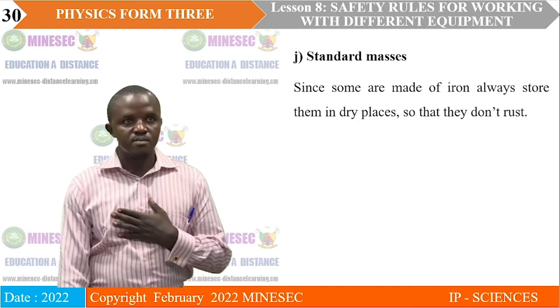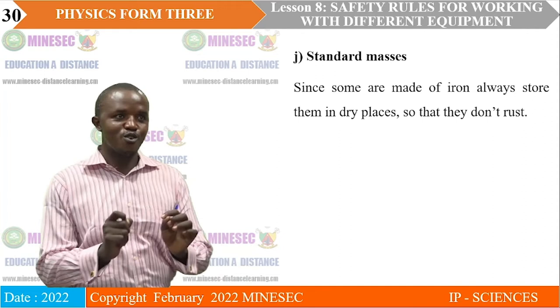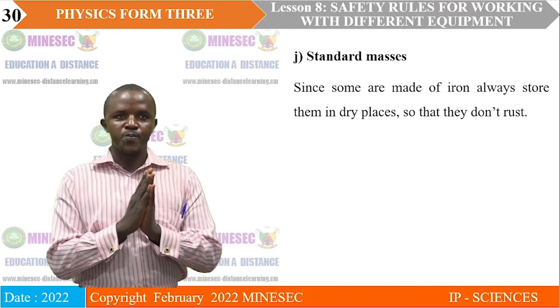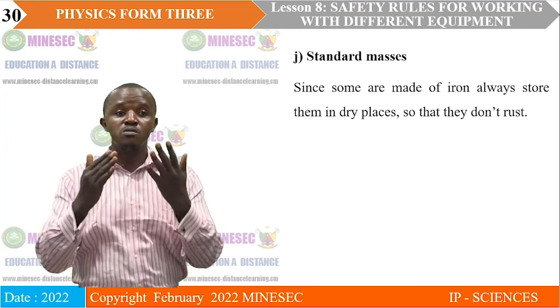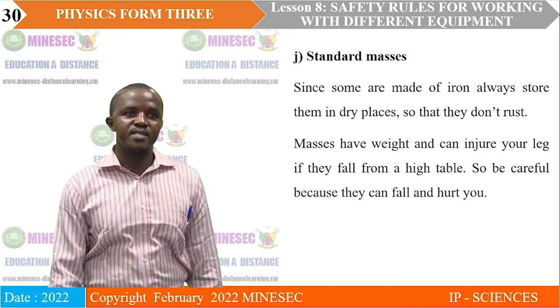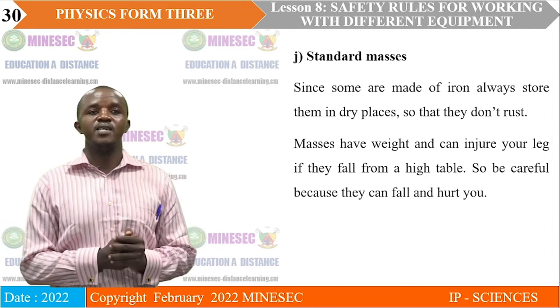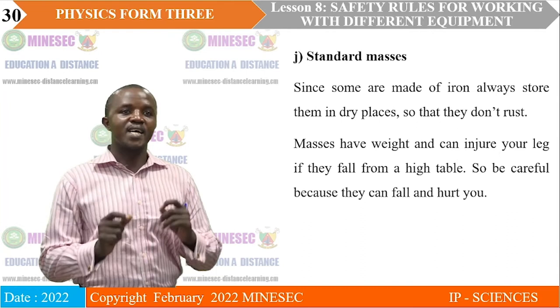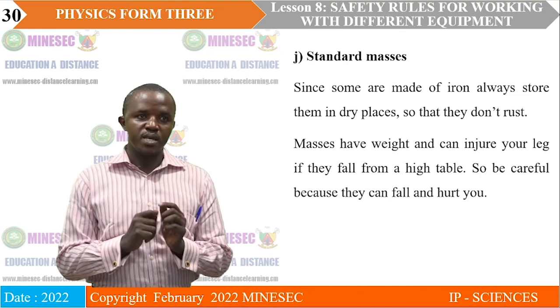For standard masses, since some are made of iron, always store them in dry places so that they don't rust — water and oxygen provide favorable conditions for rusting. The other issue with standard masses is that they have weight and can injure your leg. While manipulating them from a high table, just imagine a 500-gram mass falling on your toe — even a 100-gram mass would hurt you. So masses can fall and injure you; be careful when handling them.